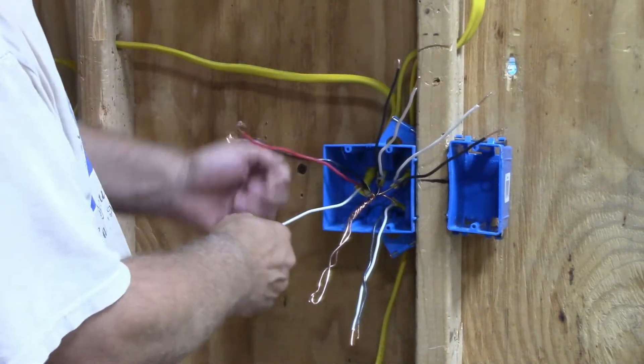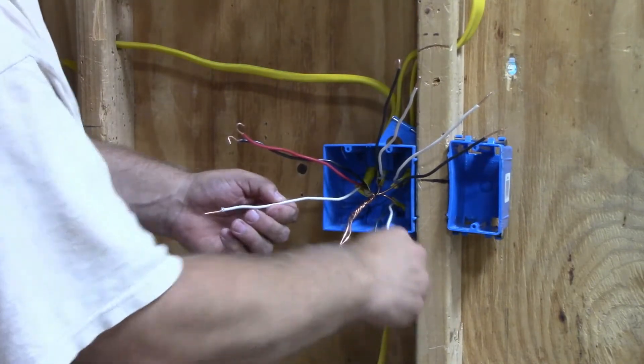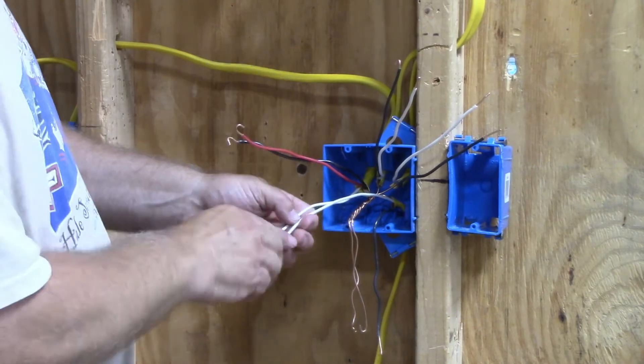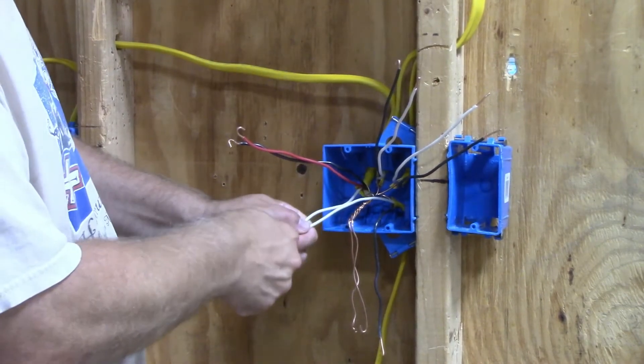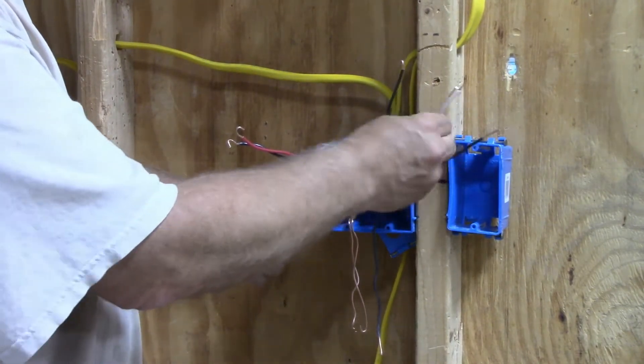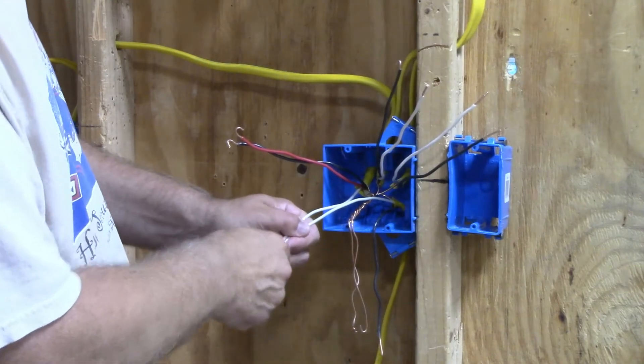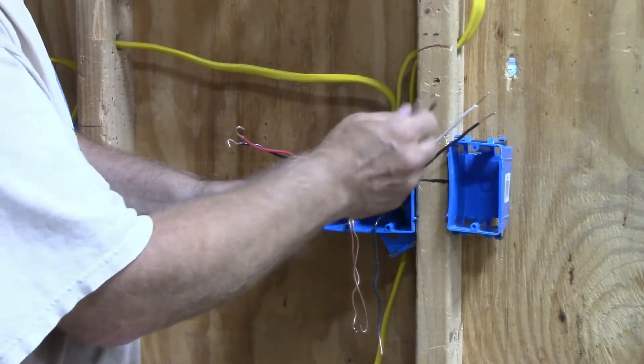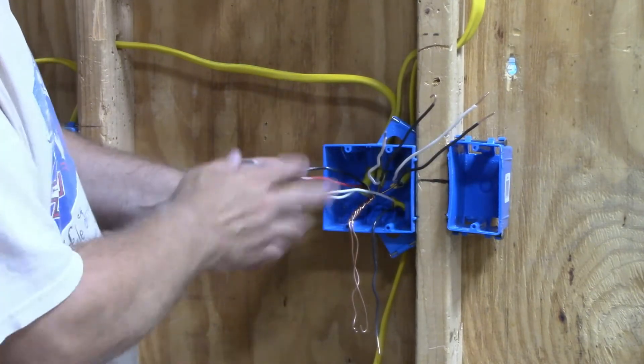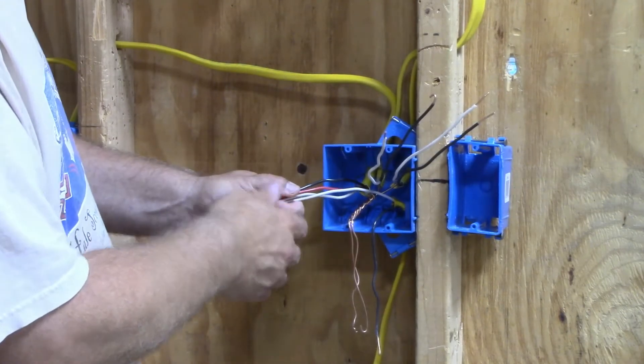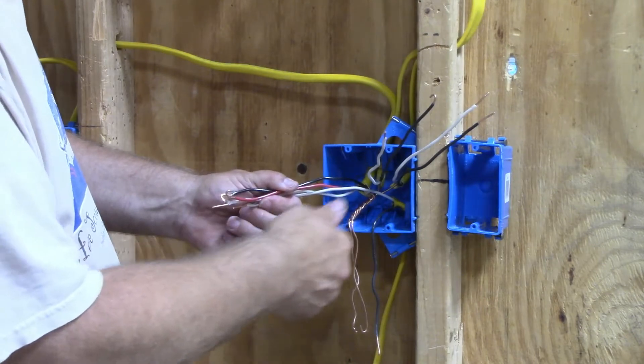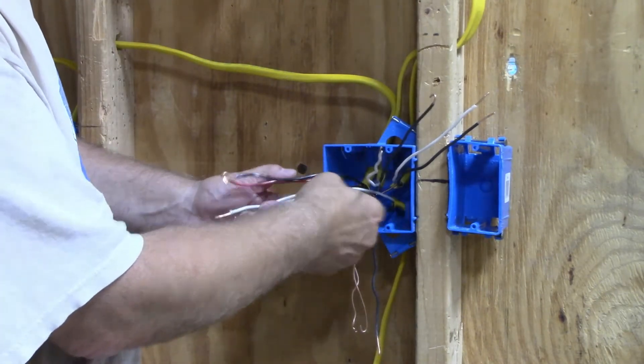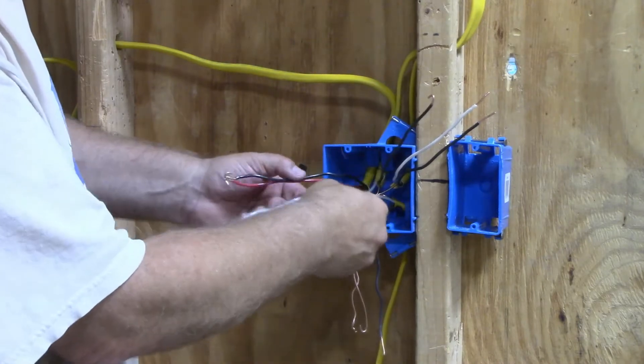When you do a box with two separate circuits, the neutral wires cannot be hooked together. I cannot take these two and hook them to these two because if I turn off this circuit and these two are hooked together, then I will get feedback through the other circuit. If I go working on it, you can get zapped. Make sure that you keep your neutral wires separate.